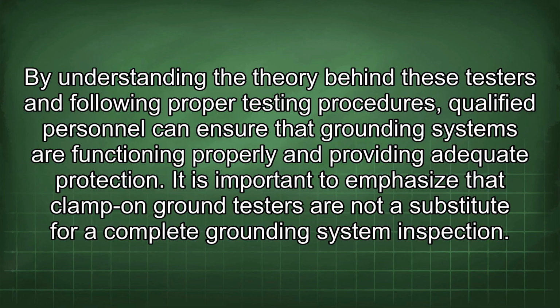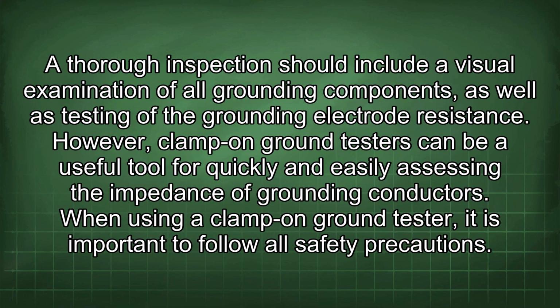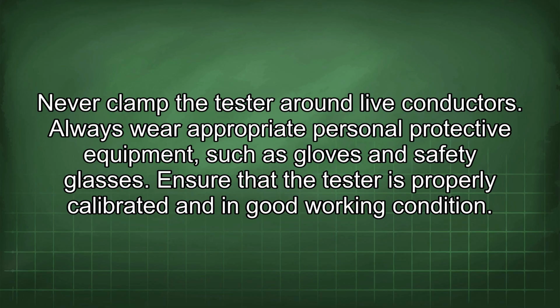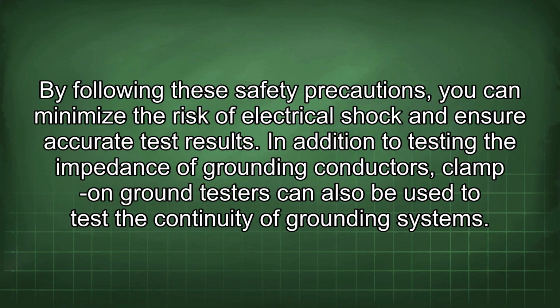It is important to emphasize that clamp-on ground testers are not a substitute for a complete grounding system inspection. A thorough inspection should include a visual examination of all grounding components, as well as testing of the grounding electrode resistance. However, clamp-on ground testers can be a useful tool for quickly and easily assessing the impedance of grounding conductors. When using a clamp-on ground tester, it is important to follow all safety precautions. Never clamp the tester around live conductors. Always wear appropriate personal protective equipment, such as gloves and safety glasses. Ensure that the tester is properly calibrated and in good working condition. By following these safety precautions, you can minimize the risk of electrical shock and ensure accurate test results.